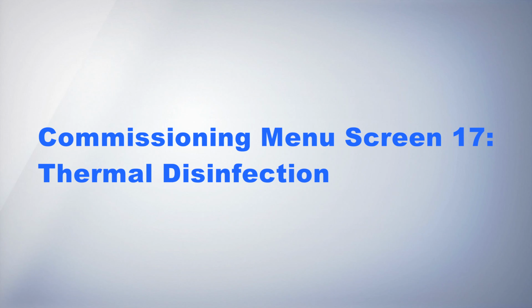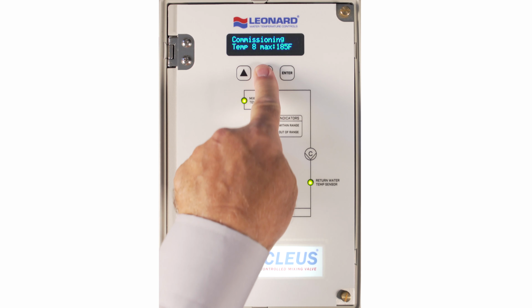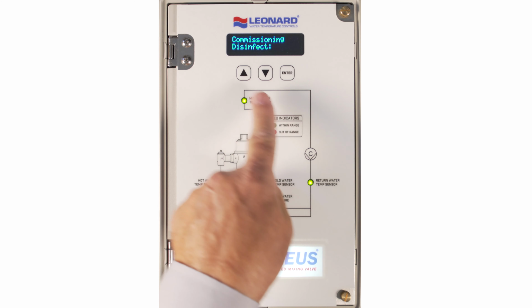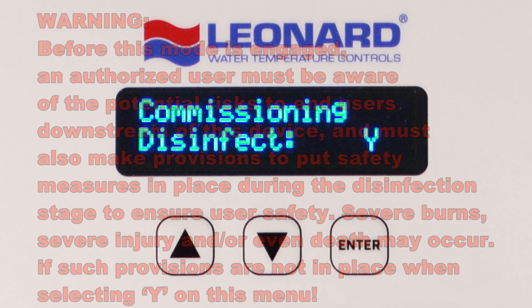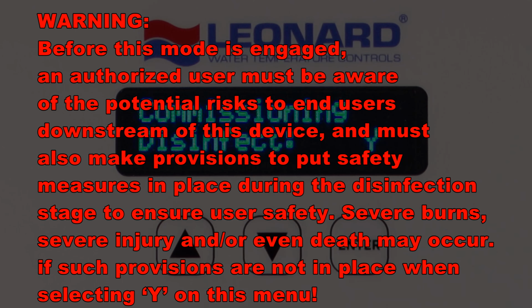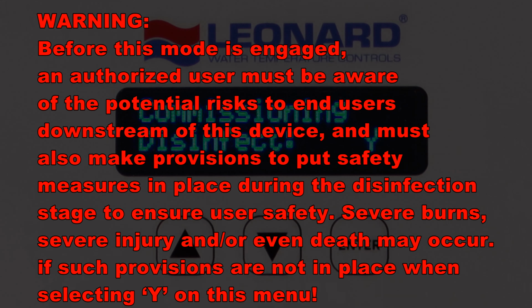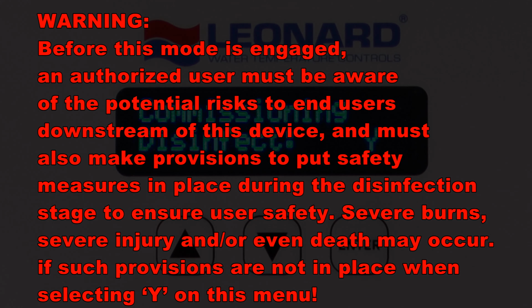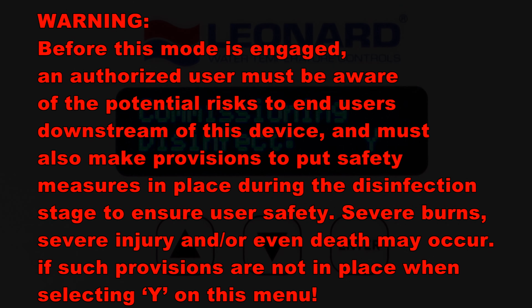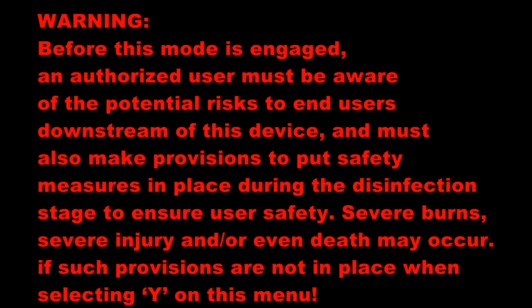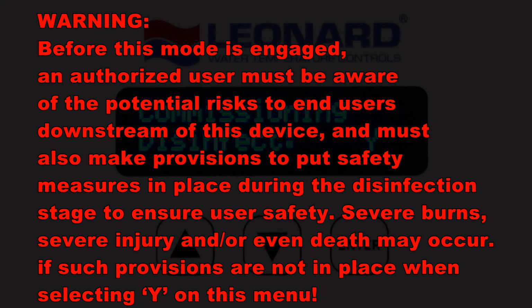Commissioning menu screen 17. Thermal disinfection. Pressing down 16 times displays commissioning disinfect, no or yes. Warning: before this mode is engaged, an authorized user must be aware of the potential risks to end users downstream of this device, and must also make provisions to put safety measures in place during the disinfection stage to ensure user safety.